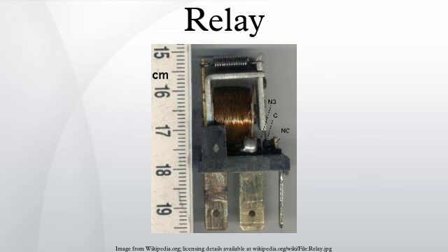Without adequate contact protection, the occurrence of electric current arcing causes significant degradation of the contacts in relays, which suffer significant and visible damage. Every time a relay transitions either from a closed to an open state or from an open to a closed state, under load, an electrical arc can occur between the two contact points of the relay. The break arc is typically more energetic and thus more destructive.